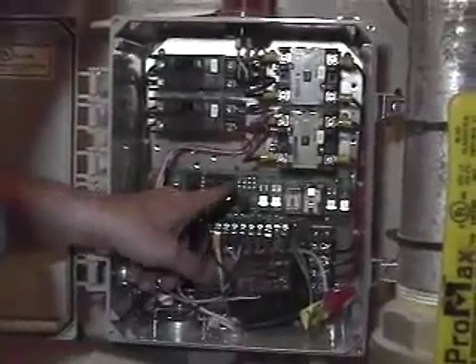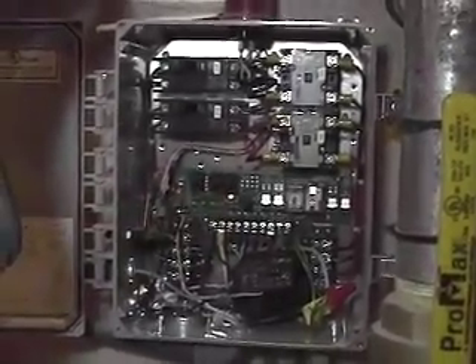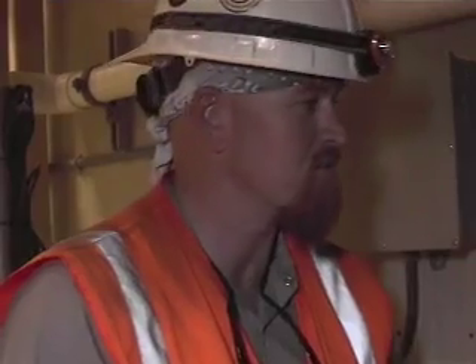Just make sure to put your switches back into auto after you've tested this, and make sure your control is still on. If you left these in off and the sump pit started to fill up, you should still get an alarm, but your pumps aren't going to be running. It would get to the point where you just hear that annoying buzzer and the light going off, and it might be something as simple as somebody forgot to put it back into auto. So that's something to remember — put the system back into auto operation.